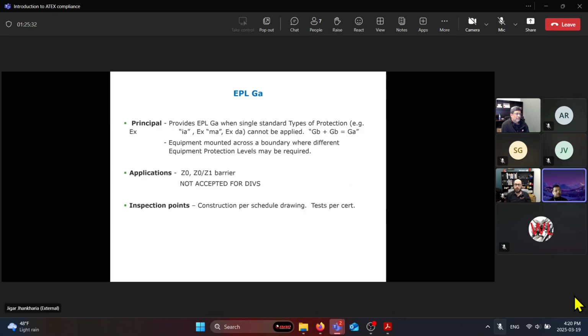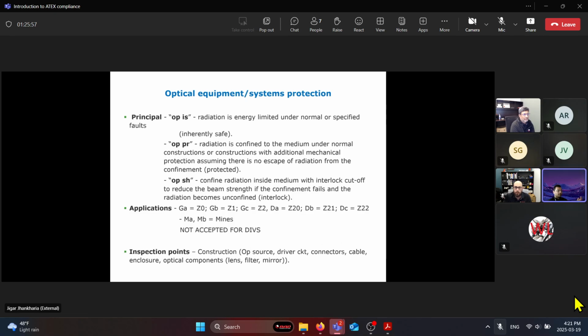So like we mentioned about the GA, GB, GC that I was talking about, depending on the zone we're certifying the product to. It provides an equipment protection level GA when single standard types of protection cannot be applied. This is again not common, so it's not applicable to your products, I would say. And then the optical radiation, again, this would not apply to something that you guys manufacture in general, in terms of tools, because it's related to optical radiation. Unless you do use any kind of optics in your product, then this is something you can consider in the future for IECEx and ATEX.